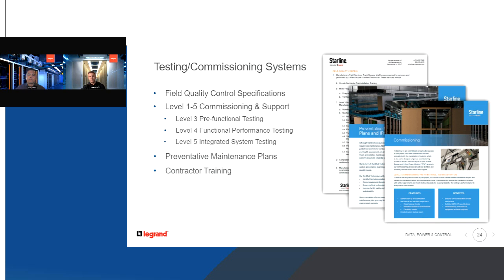Starline has developed a busway that's been tested and proven to function and work properly, and that's step one of the process. Step two is the installation - it's very important that the installer installs the busway correctly, especially with something like the Series S busway that Chris mentioned. Series S is a watertight, water-resistant busway, so when it gets installed, all the seals have to be set properly. We don't stress enough how important the commissioning side is.